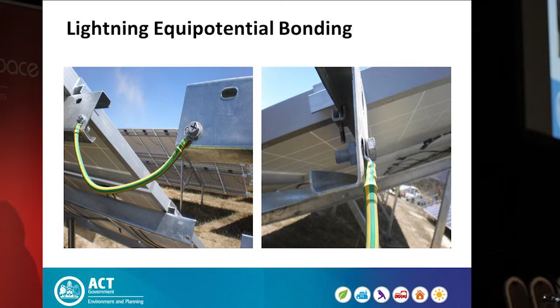Equipotential bonding, 16mm building wire used out there. Well, it's not going to survive with its... I doubt that plastic sheet's going to survive 20 years, but it's only there for the purpose of equipotential bonding now. Originally that was supposed to be the earthing, supposed to be part of the lightning protection. It's not big enough to be lightning protection. So in the end the lightning protection system was abandoned and it has no lightning protection.